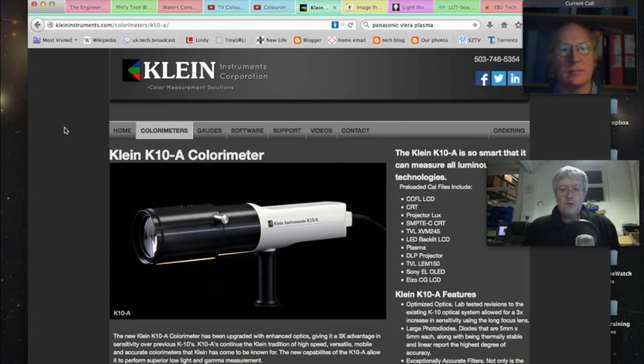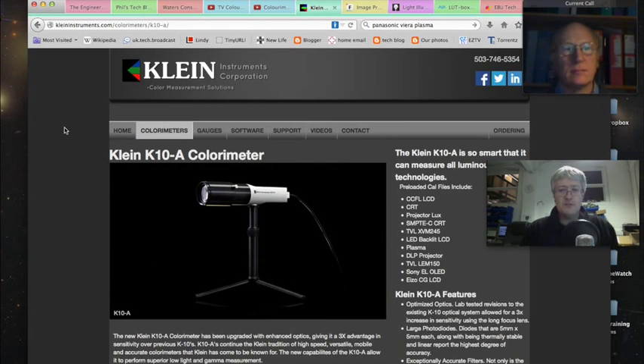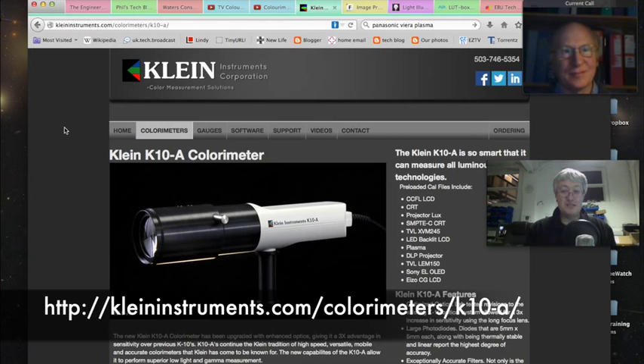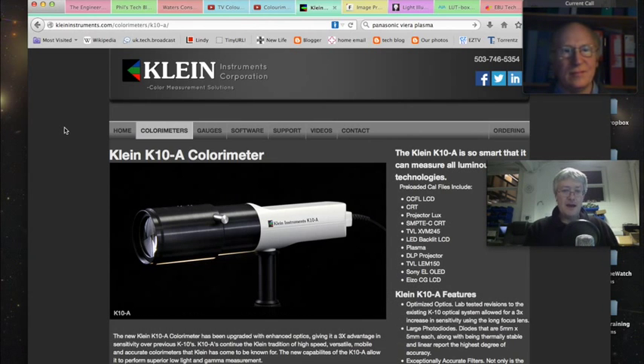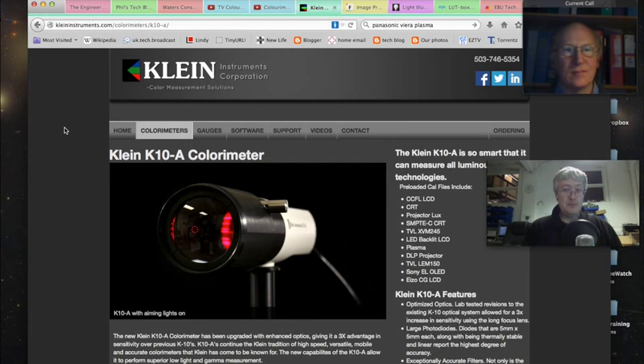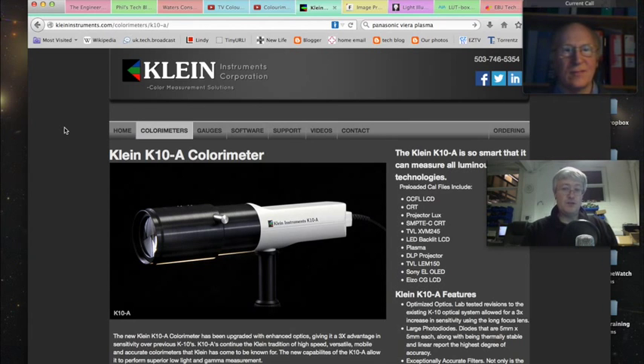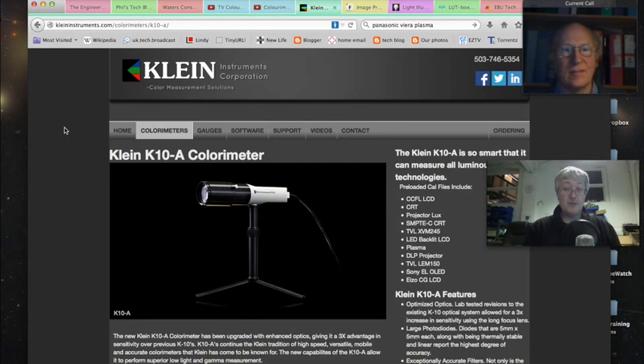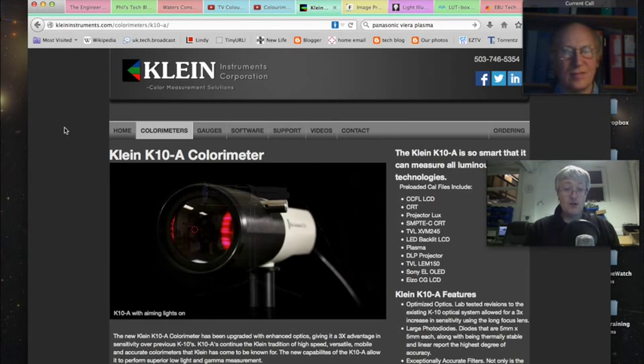If you remember from the original Colourimetry podcast, we talked a bit about the difference between spectral radiometers and photometers. The reason why people would typically schlep around with three different photometers is that each photometer is set up for the particular metameristic characteristic of the display technology it's calibrating. So the spectrum of a CRT can be best detected by a CRT calibrated probe. The spectrum of an LCD monitor, which really is the spectrum of the backlight of the LCD, is best calibrated with a photometer that's been set up for that style of display.